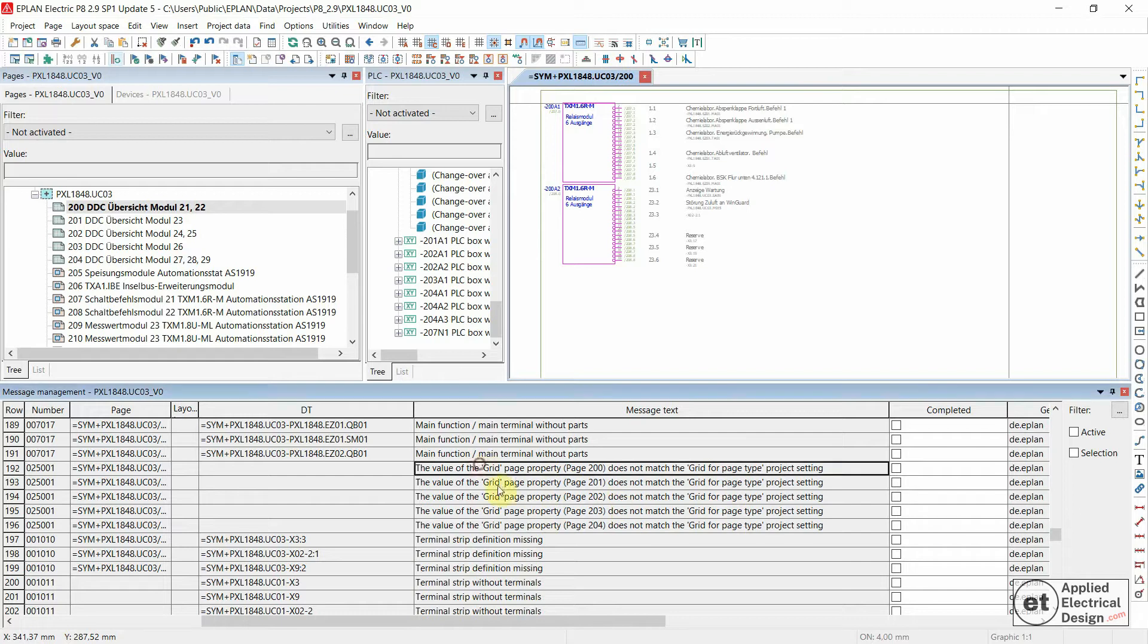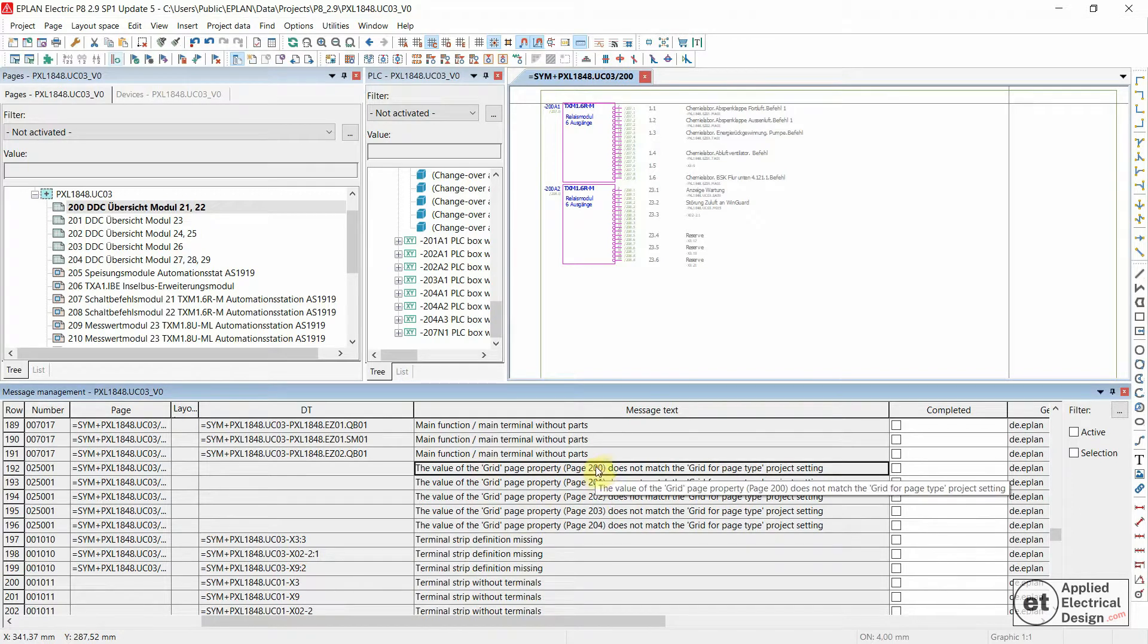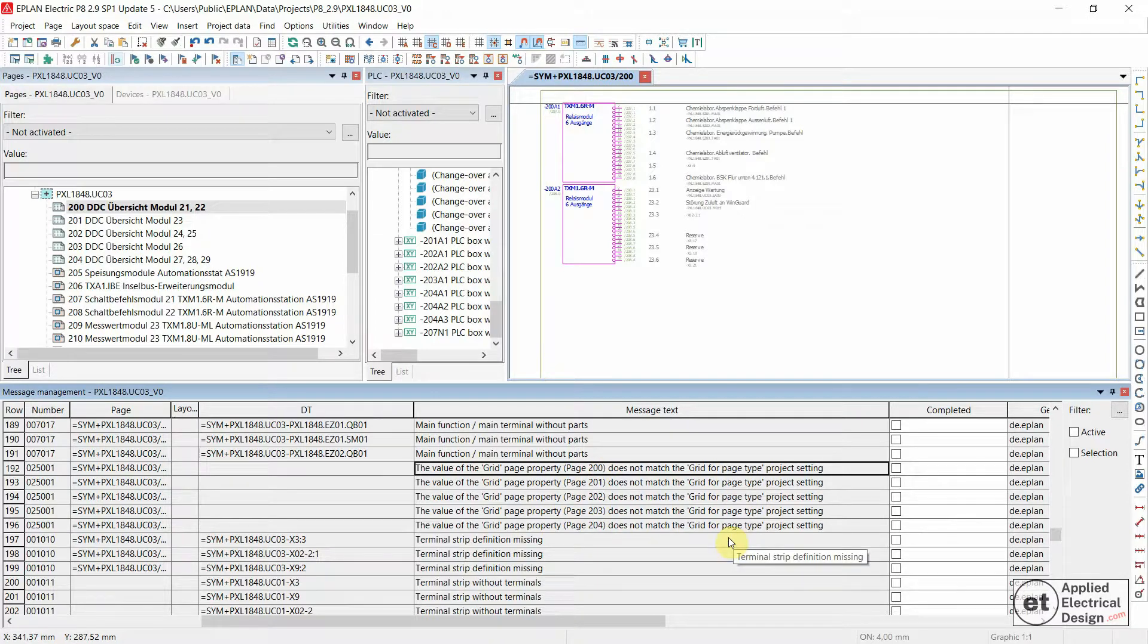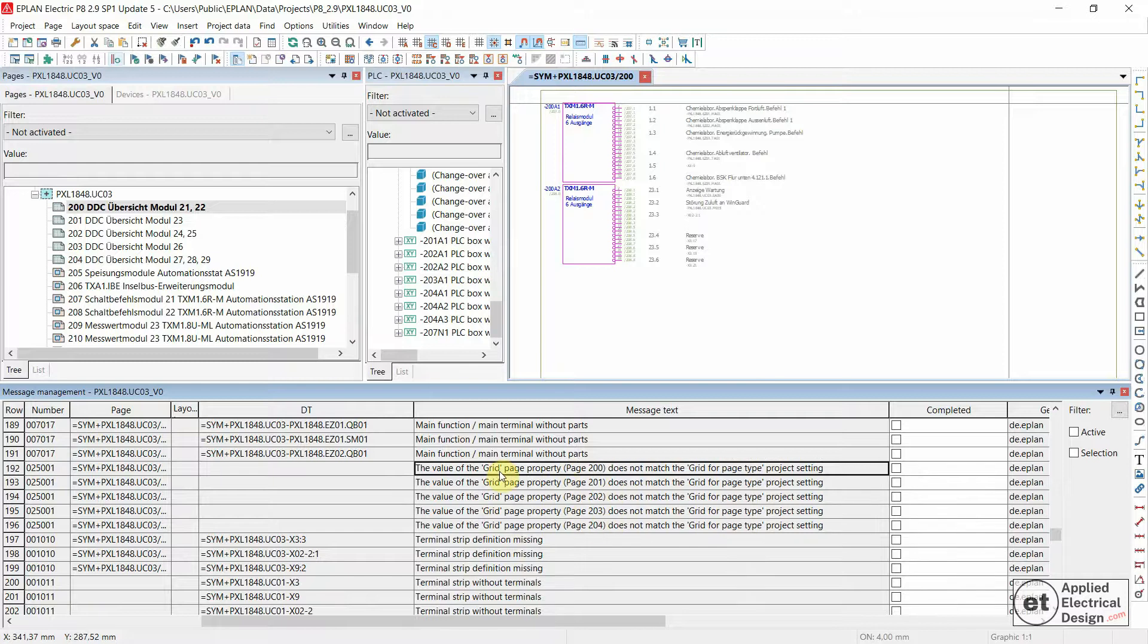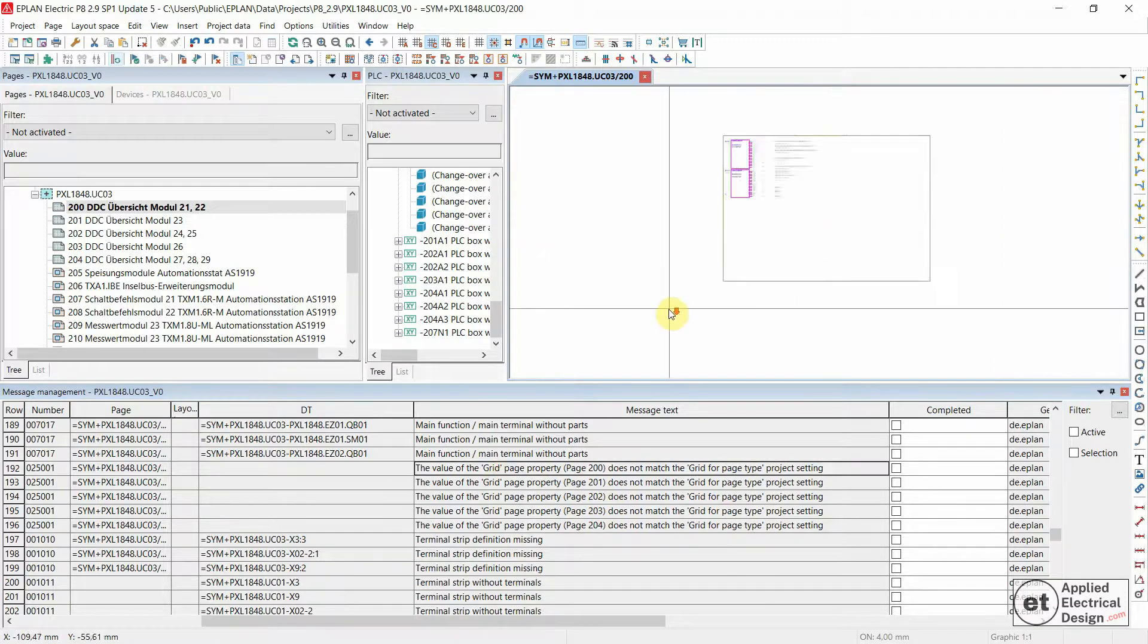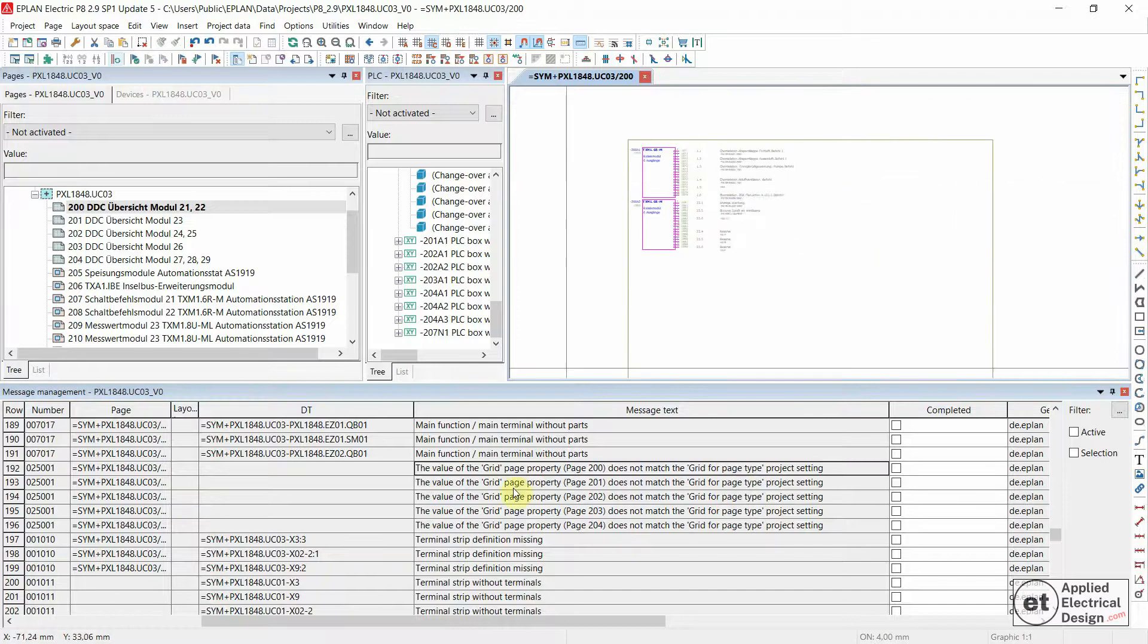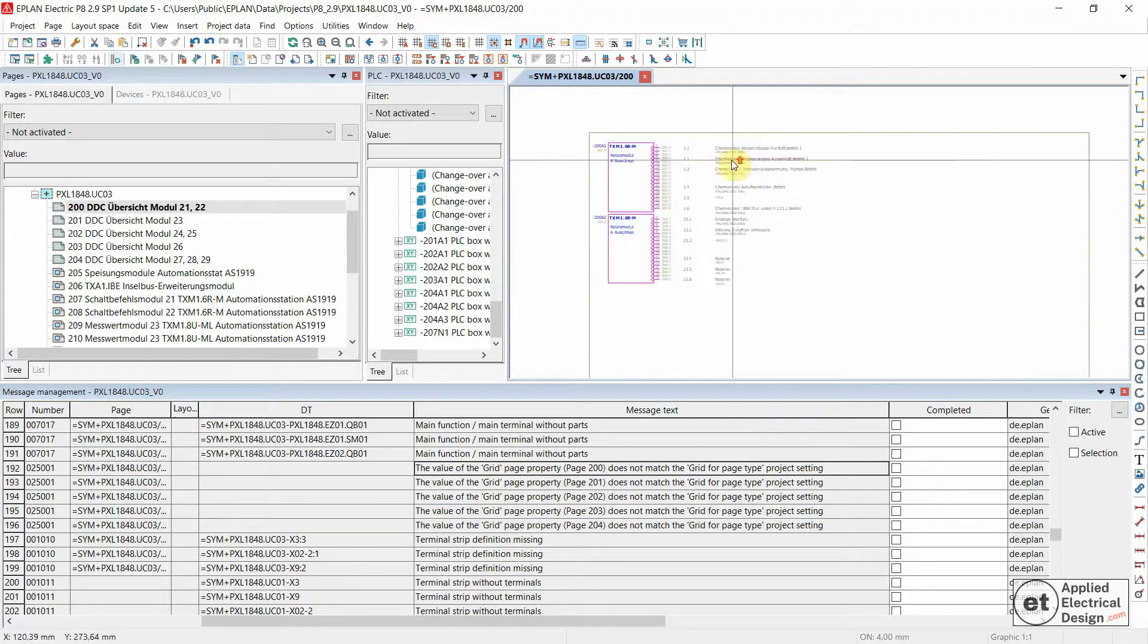The value of the grid page property, in this case page 200 to 204, does not match the grid for page type project setting. To more experienced EPLAN users, this is a pretty straightforward message. If your customer demands that you solve this message, this is how you would do that.